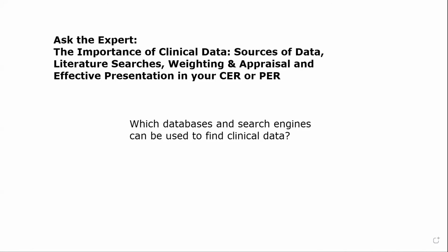The IVDR and MDR, and in fact MedDev Rev 4 most particularly, have particular requirements about this. When we remediate and rewrite new clients' CERs that have been written before, this is one of the biggest areas that we have to remediate and completely redo, because we find a lot of shortcuts or inadequate methodology has been employed by some of our clients in CERs and PERs in the past.